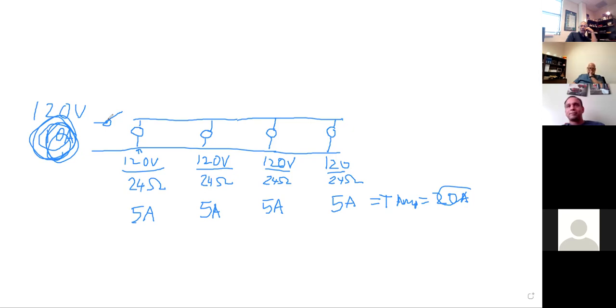That's overload. Does a breaker have a voltmeter in it? No. Does a breaker measure voltage? That's not its purpose. Does a breaker measure resistance? No. Does a breaker measure amperage? Yes. Amperage is load.